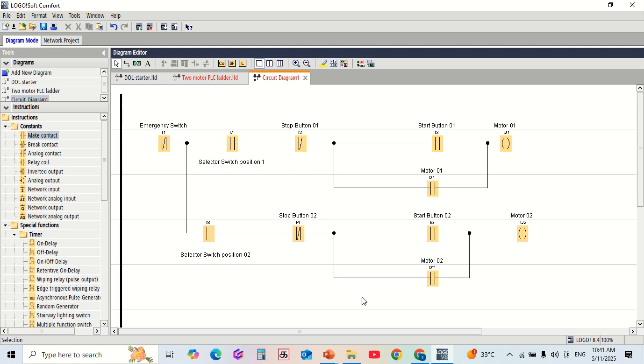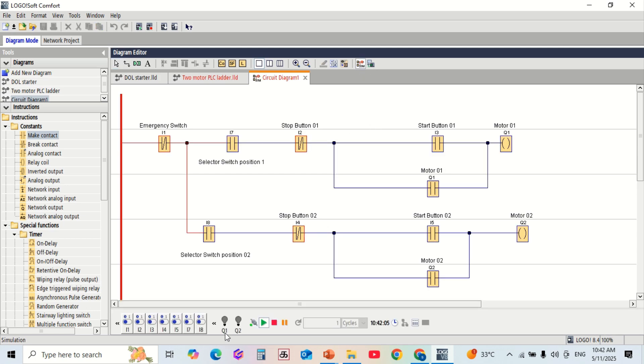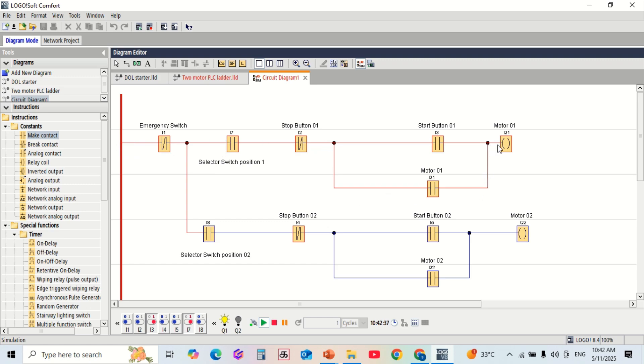Let's look at the wiring diagram. All push buttons, selector switches, and output relays are properly connected to the PLC. Each motor is connected through its own contactor. The PLC output energizes the contactor coil depending on the logic. This setup is a simple and effective way to control two motors using a single selector switch on the PLC.